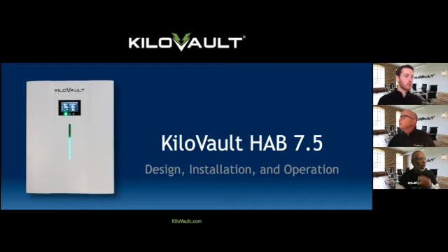Another question from Gail: does set point need any temperature compensation? No, it does not. You do not need to do any temperature compensation with the HAB. So if it requires that you put it in, then you put in zero millivolts per degree.